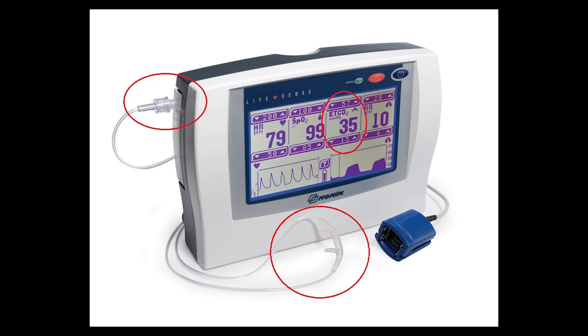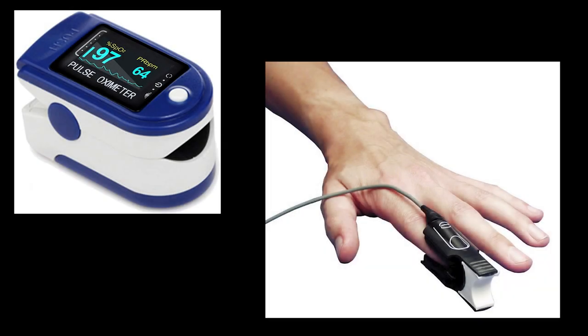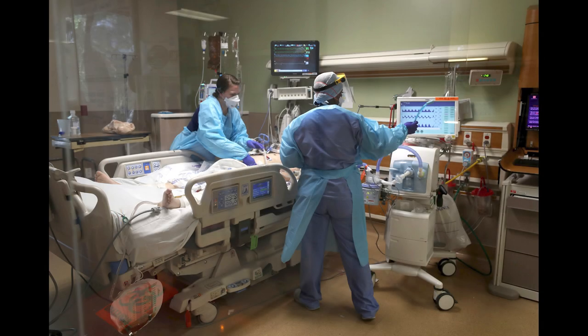Normal numbers for a healthy patient are around 35 to 45 millimeters of mercury. Both SpO2 and end-tidal CO2 are vital methods for monitoring a patient's health, and each has its best use case scenario. Most people are familiar with pulse oximetry, as it's been at every patient bedside monitor for around the last 20 years. Hospitals are taking a strong initiative to incorporate end-tidal CO2 monitoring as a standard of patient care, because it's been proven to alert on health complications much faster than SpO2. Every second counts when you're dealing with a cardiopulmonary emergency.